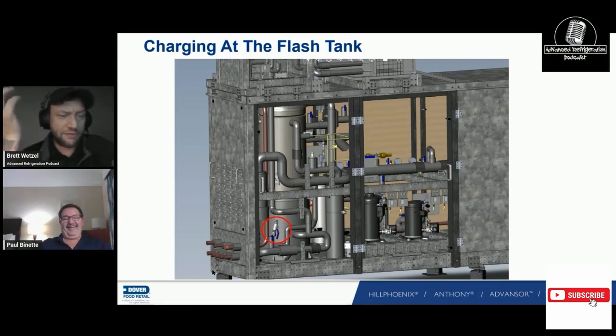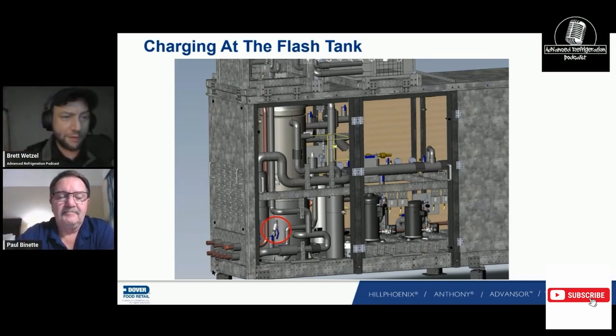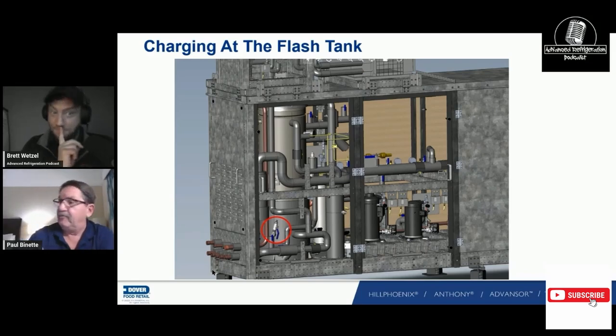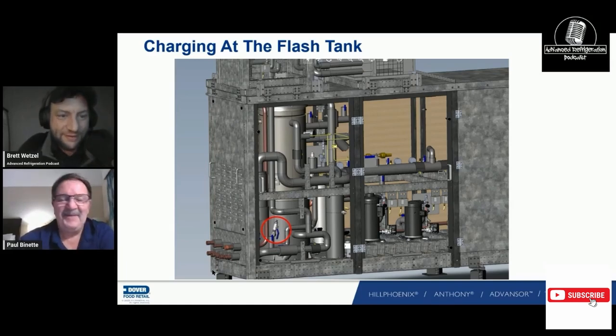When ordering CO2 for training, I asked for one vapor bottle and the rest liquid — I said I'll be making my own vapor cylinders as time goes on. In the field when all you had was liquid bottles, there's the old technique of putting them upside down to get vapor out — which I'll deny everything about. When contractors pump down the rack for service and need to pressurize liquid and suction lines again, Hill Phoenix says bring your lines up to 150 PSI before introducing liquid — well above the 61 PSI triple point. That 150 PSI reference also lets you check all your case controller transducer calibrations at once, noting which read high or low.